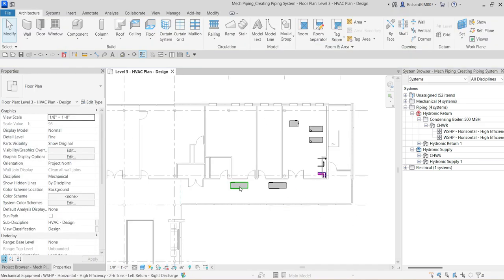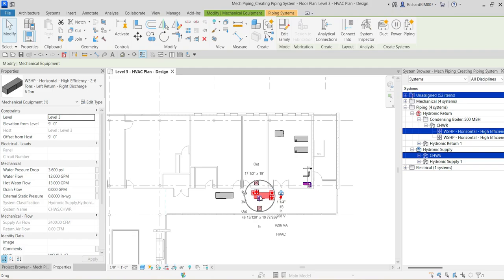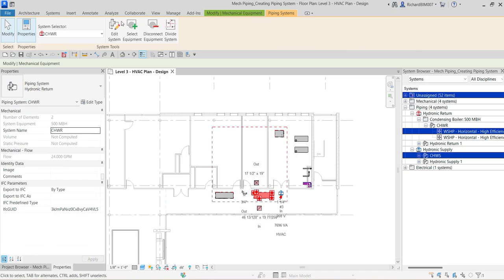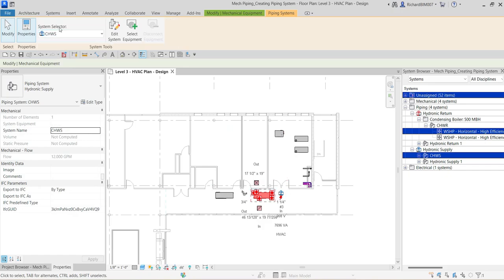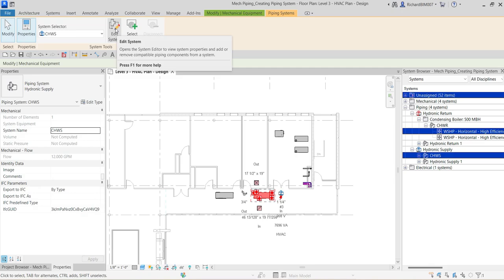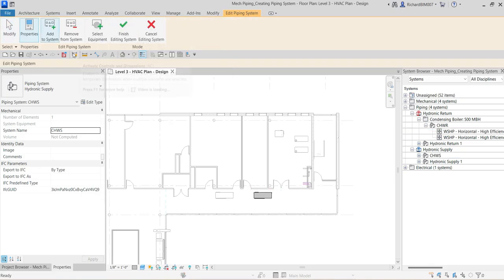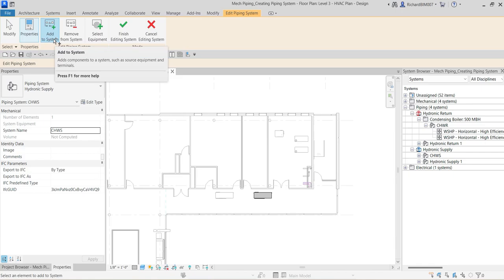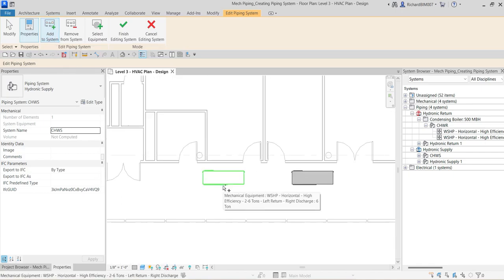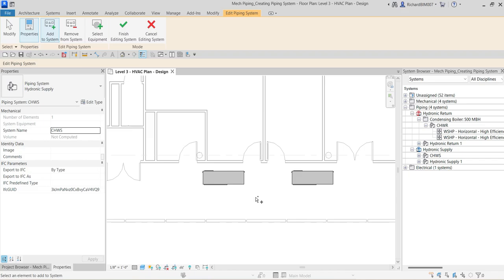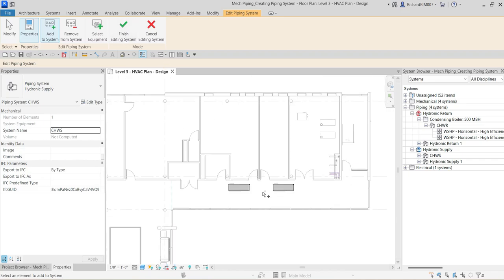Now I want to add the second water source heat pump and additional equipment. I'll select the heat pump, then go to Piping Systems again. On the system selector, make sure CHWS (chilled water supply) is selected. Then I'll click 'Edit System.' The equipment is already selected by default — I'll add it to the system. Before finishing, I want to change the level and navigate to a different view.